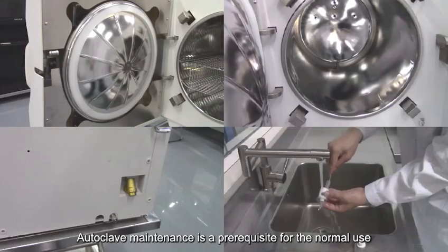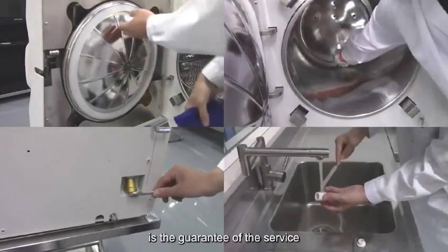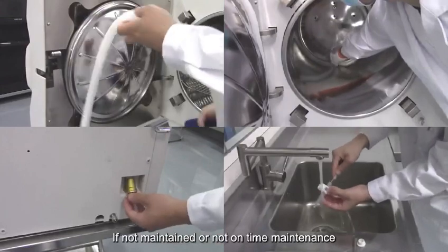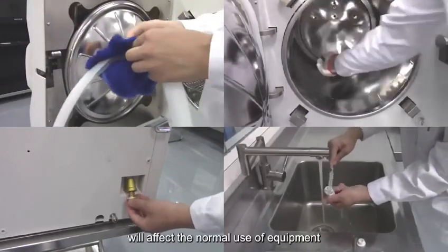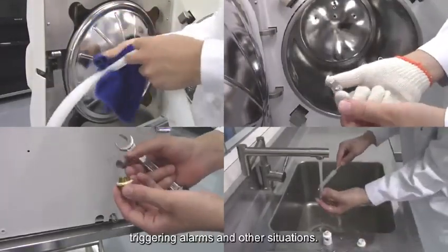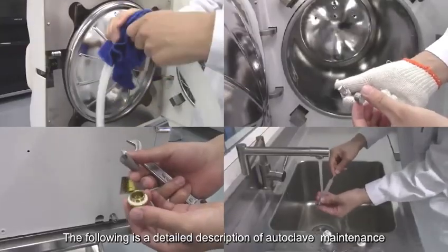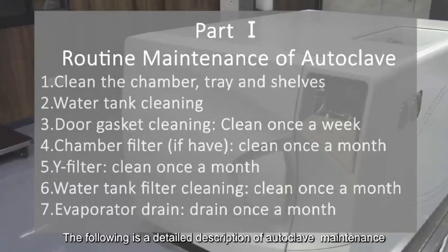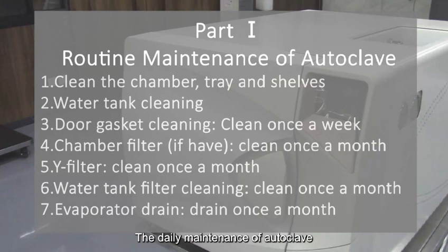Autoclave maintenance is a prerequisite for normal use and is the guarantee of the service. If not maintained, or not maintained on time, it will affect the normal use of the equipment, triggering alarms and other situations. The following is a detailed description of autoclave maintenance. The daily maintenance of the autoclave mainly includes the following 7 aspects.